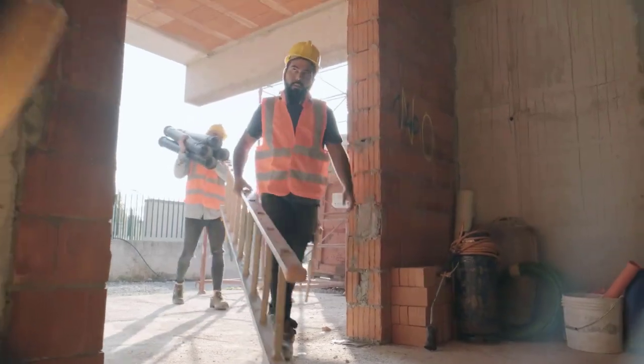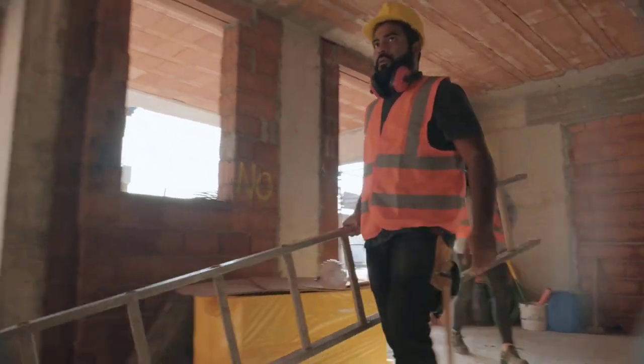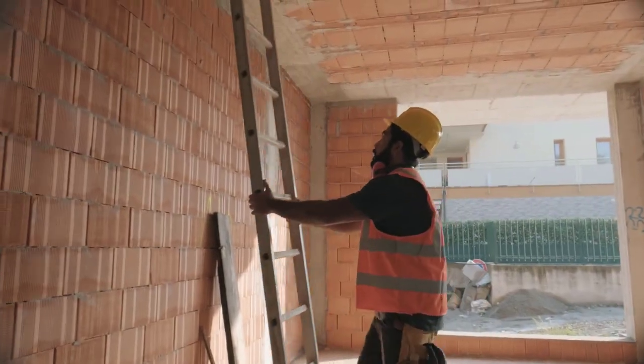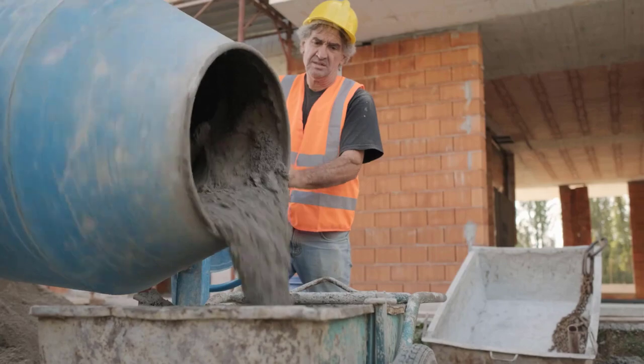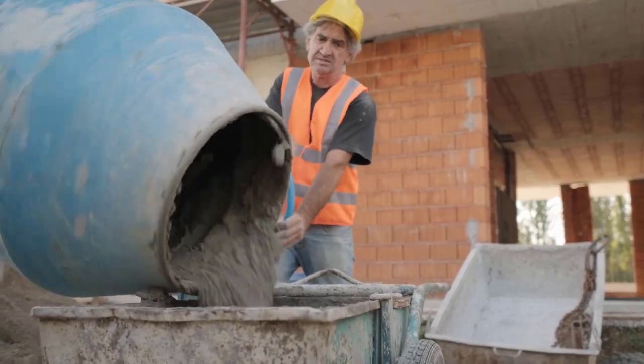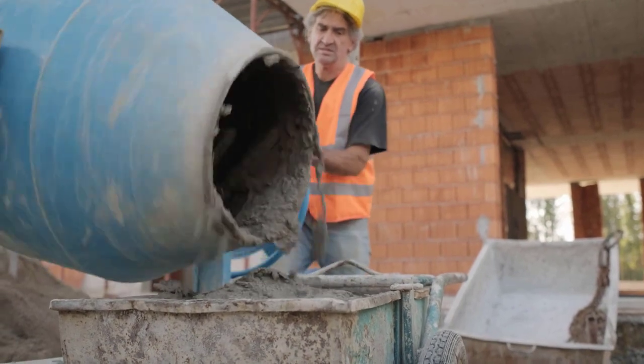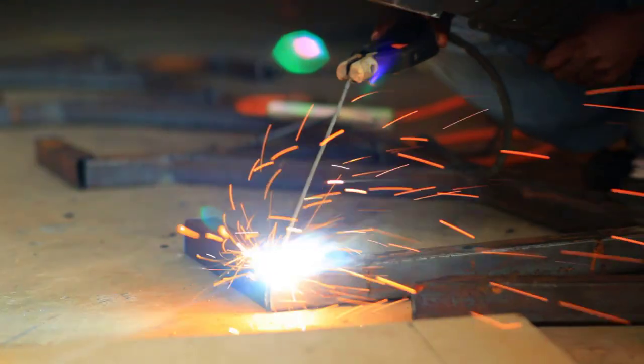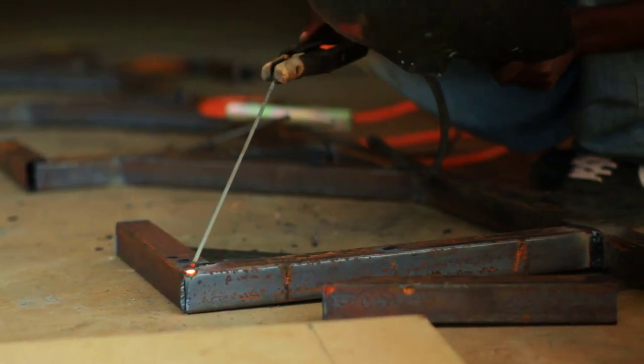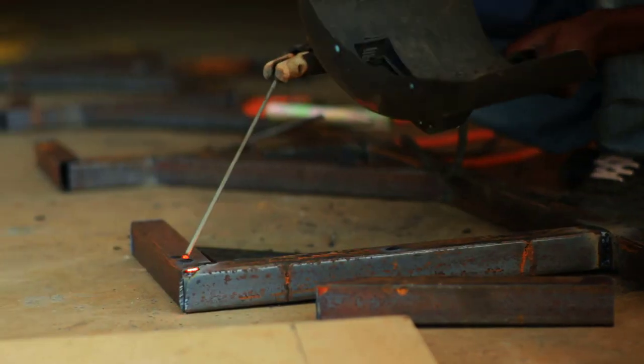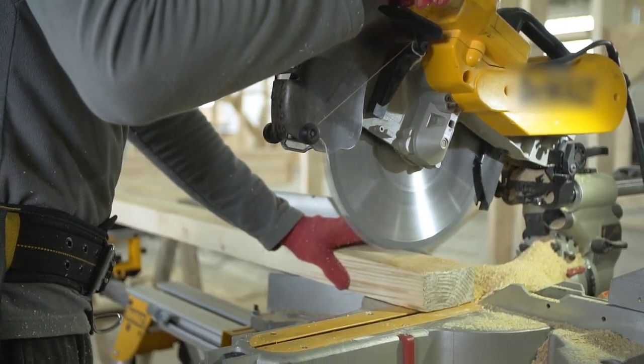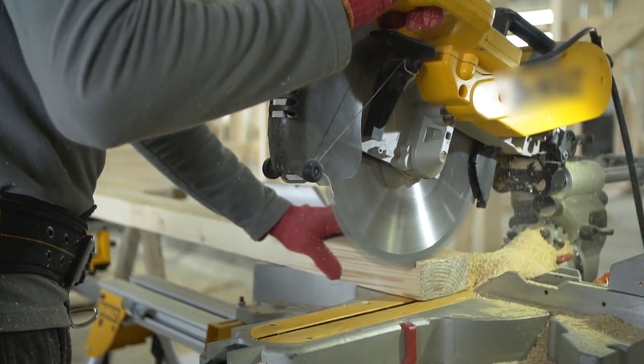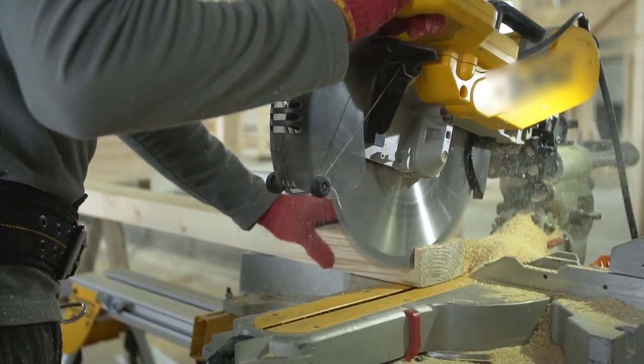We'll now talk a little bit about training. The fire safety manager shall ensure that all construction site personnel are familiar with the operation of portable fire extinguishers and other fire protection equipment on the construction site. All workers on site must receive orientation. They will be retrained every 6 months. All workers that are involved in hot work operations will receive hot work orientation. They too will be retrained every 6 months. The construction site fire safety manager must file copies of all certificates of fitness on site upon FDNY inspection.